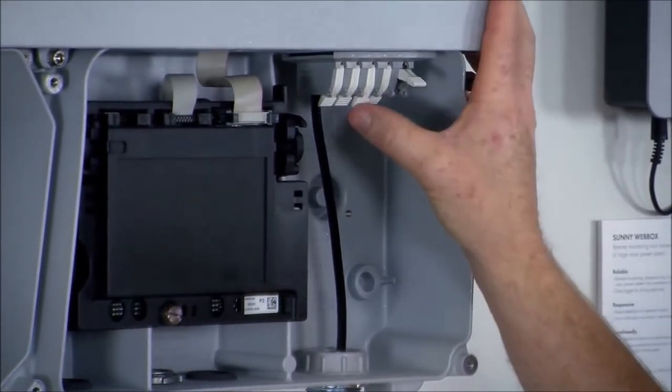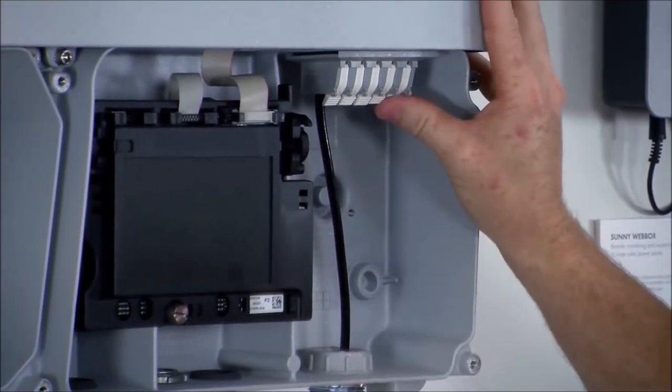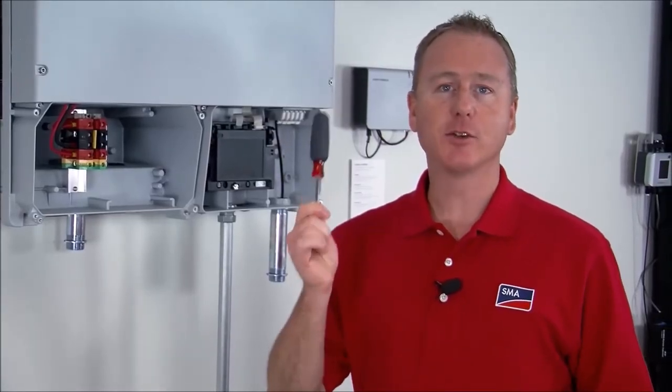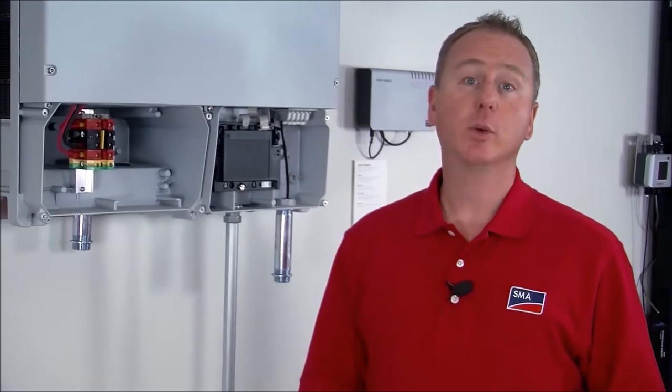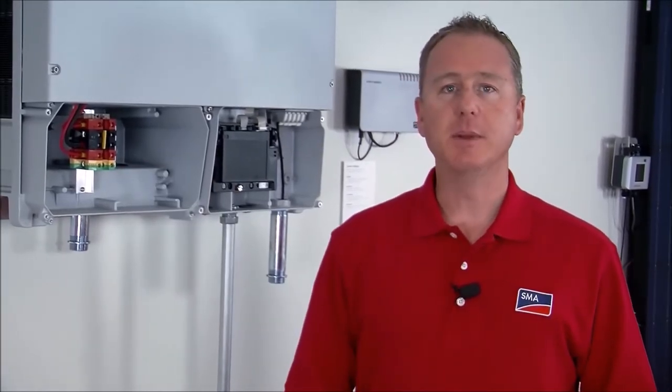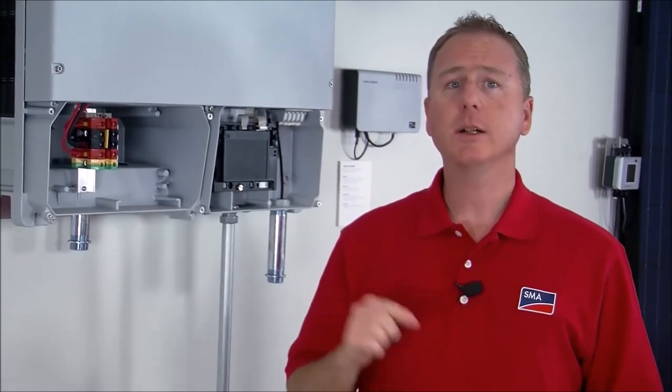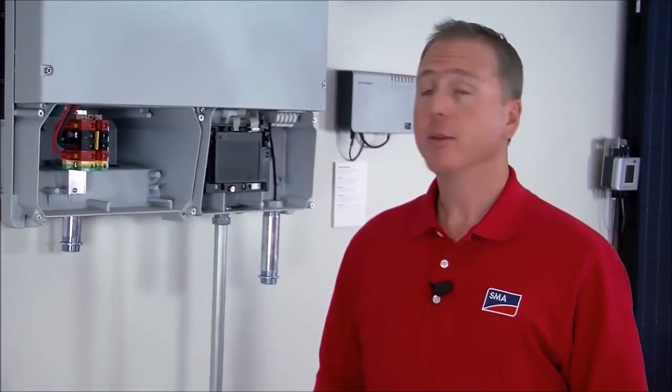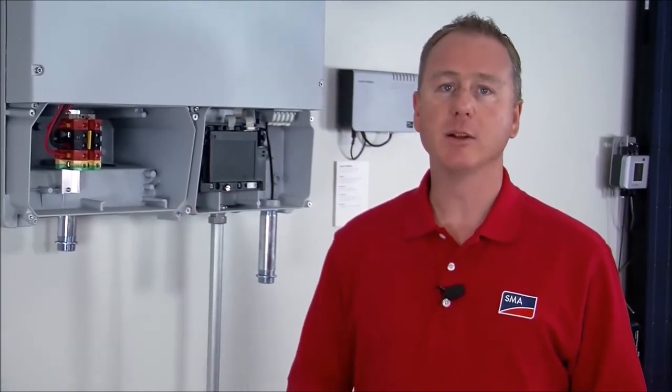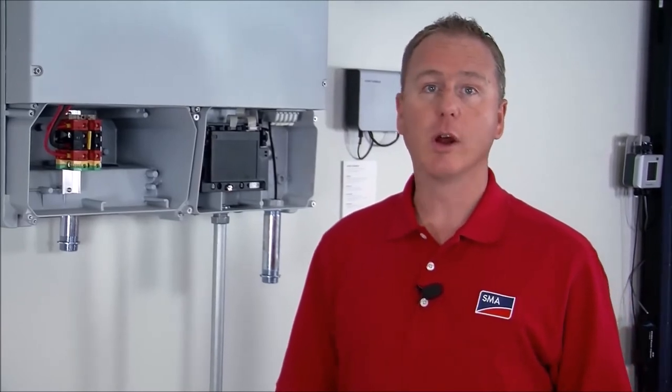Now for the DC side we're back to using our trusty screwdriver, a number 2 will suffice, and the conductors that will land in these terminals can be anywhere from a number 2 to a number 8. Now you want to check the manual but the proper torque spec for these terminals is 51 inch pounds so we really recommend that you get a torque screwdriver.